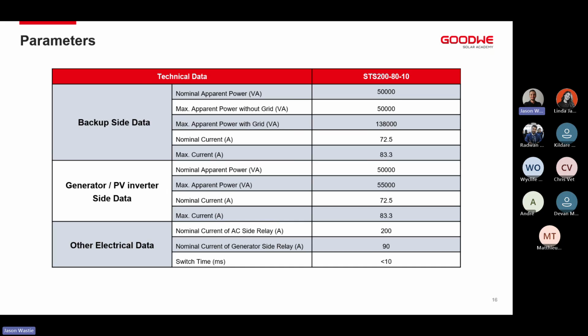The physical AC relay on the backup output port is 200 amps, meaning we can put a total of 138 kilowatts through the backup port. That means we can have additional contactors installed, so we don't necessarily have to split the DB board immediately. When the grid is available, we run the 138 kilowatts on your site, and if the grid falls away, we can open those contactors, which removes some of the load, and you go back down to the 50 or 55 kilowatts output that the inverter can allow in backup mode.